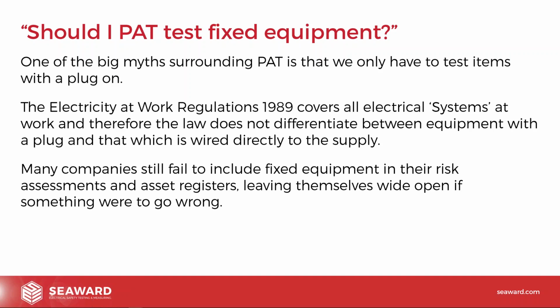And a lot of companies, if you want to know how good somebody's PAT testing system is in a company, generally have a look at things like their hand dryers, the water boilers, the cookers. Those sort of things generally are the bits that get missed. And the problem with that is that they fall in the gap between the fixed installation testing, the electrical installation condition reports, the EICRs, and what would be traditional PAT testing.